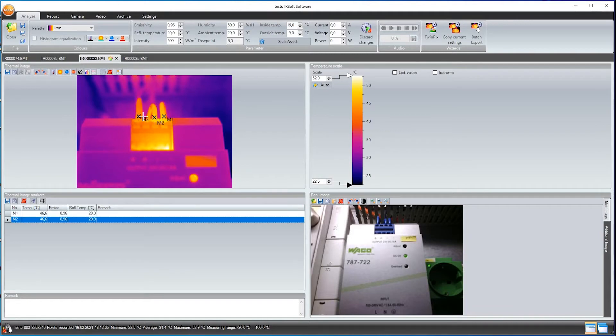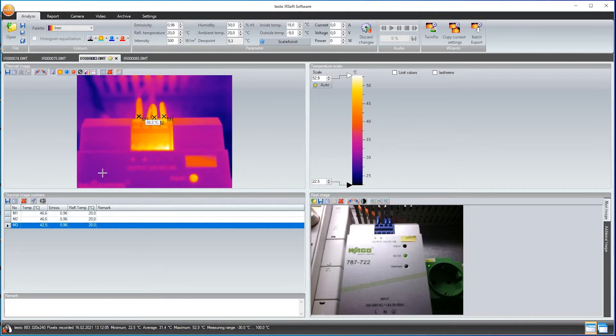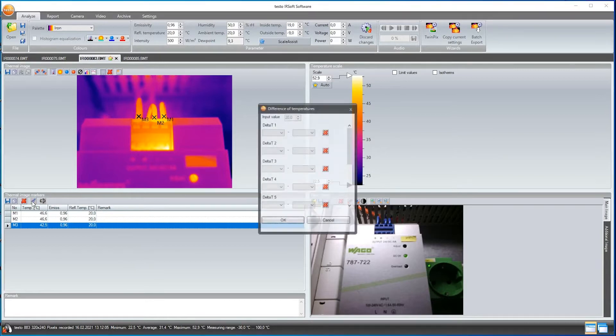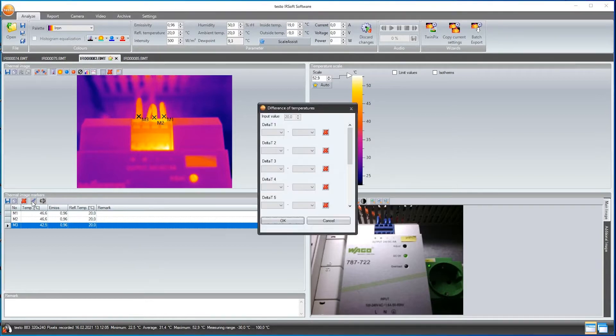I can enter a comment for each point in the table under the thermal image. In Thermography of Electrical Components, temperature difference between the phases plays an important role. I can have this calculated for me easily by selecting the tool Delta T at the thermal image markers.